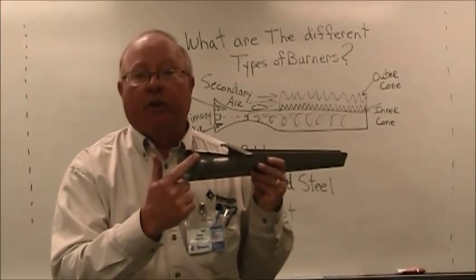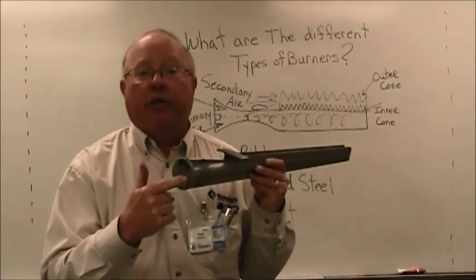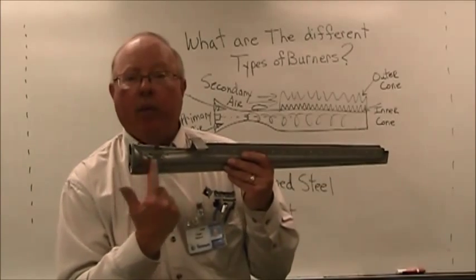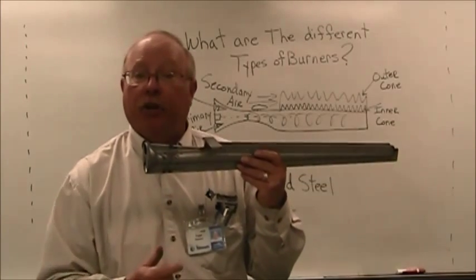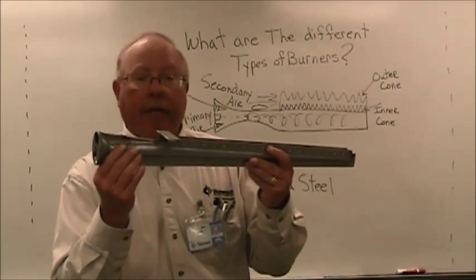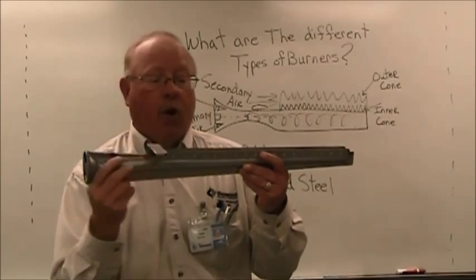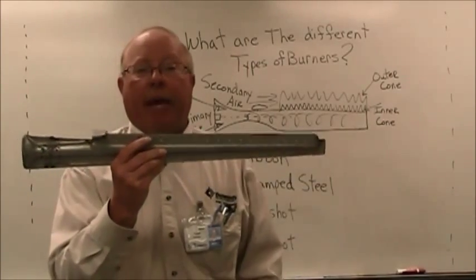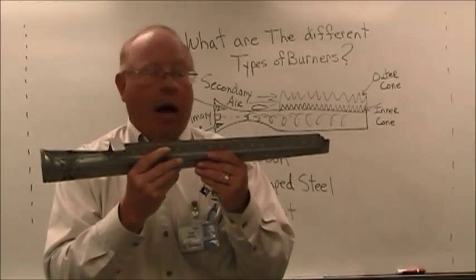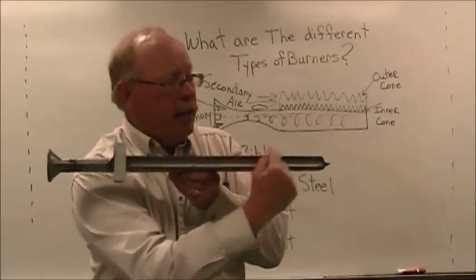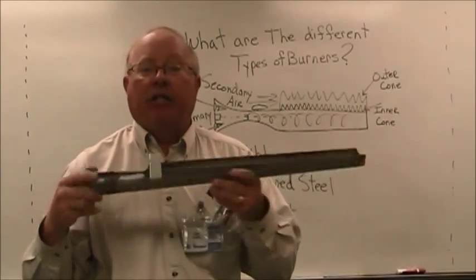This burner has all the accoutrements that are found on every burner. It has the wide mouth entrance where the primary air is going to enter, and the gas through the orifice. We have the narrowing, which is the venturi. The venturi throat allows for the fuel and the primary air to go down into the mixing chamber, and then from the mixing chamber to be spread evenly at the base of the burner.